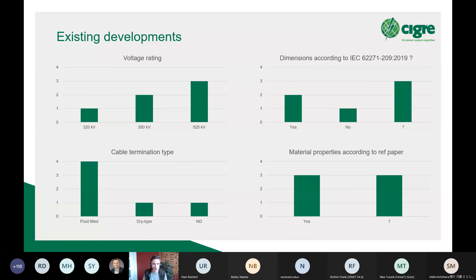It should be noted that when it says fluid filled, for example, in the IEC 62271, this really refers to a set of dimensions, for example, long or short dimensions, which can then also be used in the HVDC version, except that it doesn't mean that it has to be fluid filled. So it could actually be a dry type design with the dimensions of a fluid filled type cable connection assembly. Then we looked at the different types of cable termination arrangements or designs that are out there, and the significant share was made up by the fluid filled design. So in this case, it would be SF6 filled, but dry type designs also exist. And then lastly, we wanted to know a little bit about whether the material properties are comparable, and in most cases that seems to be the case.